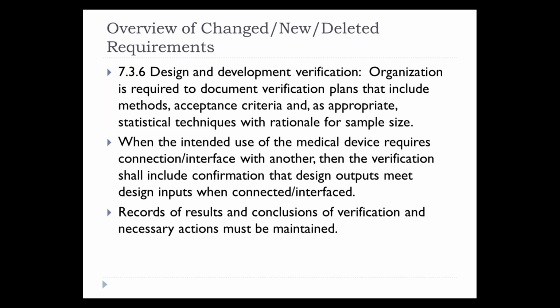When the intended use of the medical device requires a connection or interface with maybe another component, then the verification has to include confirmation that the design output meets the input requirements when it is in fact connected or interfaced with another piece of hardware or software or another component. The records of the results and the conclusions of the verification and any necessary actions resulting have to be maintained.